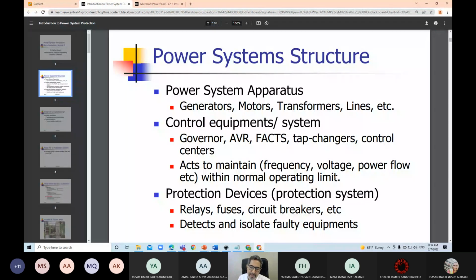But these limits are very small. And you don't think, oh, I have a big margin. For voltage, let's say, you have within 5 percent limits. Now, if you reach 10% or higher, there will be a dangerous voltage. You should act, something has to be done to overcome this high voltage. Otherwise, there will be damage, okay, to the equipment.